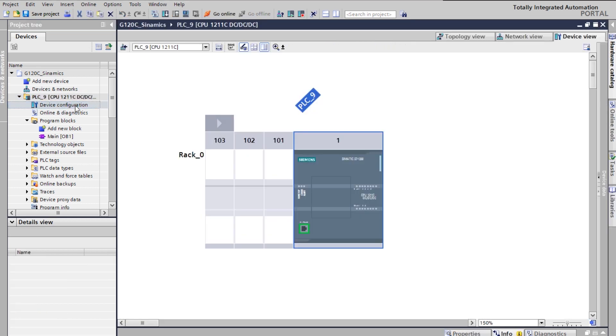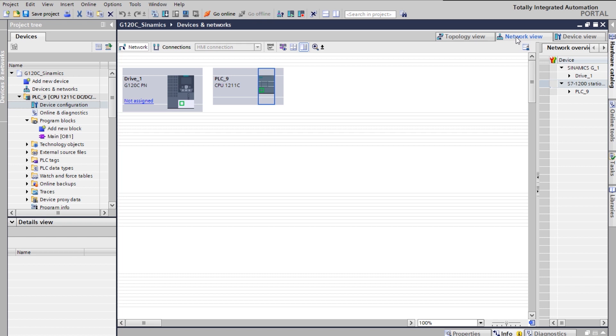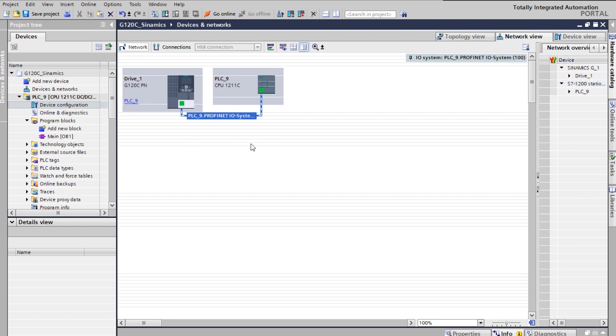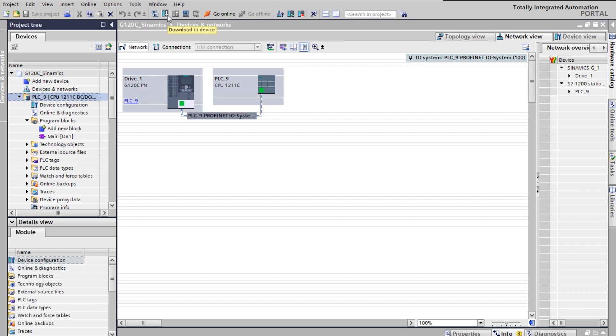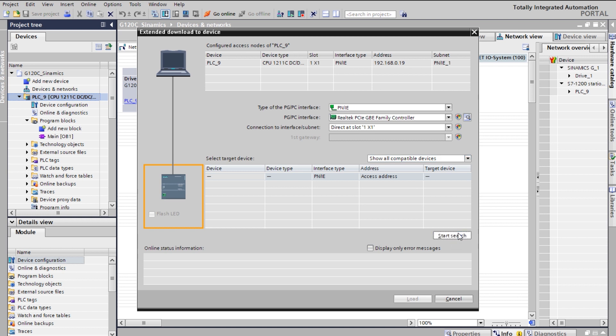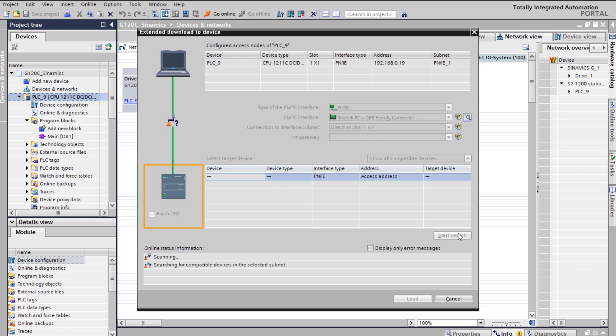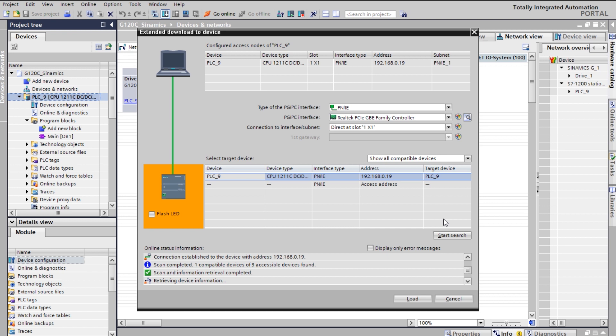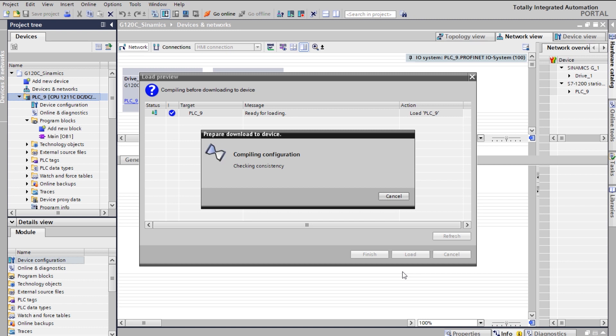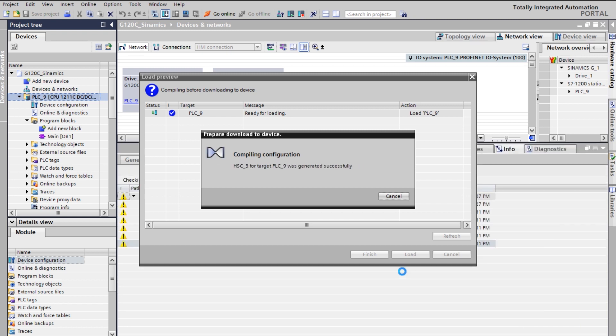Before that, we need to connect this PLC to the G120C drive. Open device configuration, click on network view, and here you need to connect the PLC with the G120C drive. You can see the connection is established via PROFINET — your G120C is now connected to PLC9. Click on the PLC and then click Download so that all configuration changes will be downloaded into the PLC. You can see the PLC has been detected in the network — click Load so your program will be loaded into the PLC.